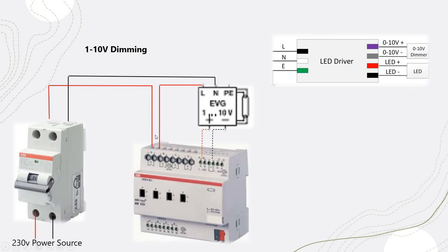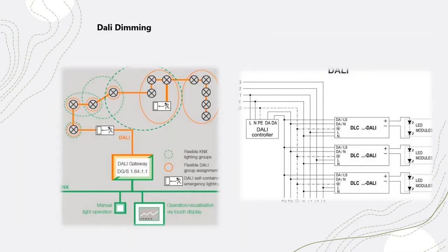The reason we pull the live cable from the 0-to-10V dimmer actuator is to control the lighting switching — on and off — while the dimming is controlled through the 0-to-10V signal channel. It's somewhat similar to DALI but the key difference in DALI is that every light has an individual address, unlike phase dimming and 0-to-10V dimming.